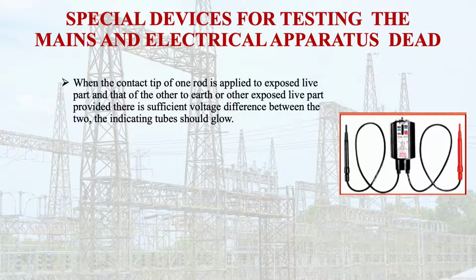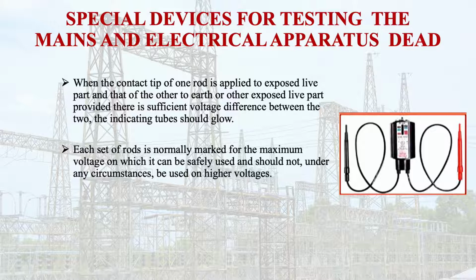When the contact tip of one rod is applied to an exposed live part and that of the other to earth or another exposed live part, provided there is a sufficient voltage difference between the two, the indicating tubes should glow. Each set of the rods is normally marked for the maximum voltage at which it can be safely used and should not under any circumstances be used on higher voltages. It should be ensured that all the devices for proving the high voltage mains and apparatus dead are marked clearly with the maximum voltage for which they are intended, and should be tested periodically as per the manufacturer's guidelines.